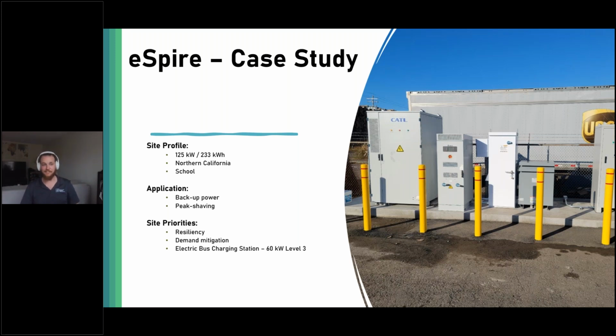But in addition to that, you can see at the bottom, they were also adding a relatively small level 3 EV charging station for electric bus. So they realized, hey, our power demands are going to be much more than they were before. It's going to affect our power bill. We need a way to mitigate this demand, especially if down the line they go to add even more level 3 chargers. So the dual use here of backup power plus peak shaving, by far being able to stack that value is the best way to help these systems pencil. And in this case, it made great sense for backup power and peak shaving. Now, one thing that this system is future-proofed for, right, that wasn't necessarily ready when we installed on site is virtual power plant, right? All the utilities across the country really are starting to roll out these virtual power plant programs.